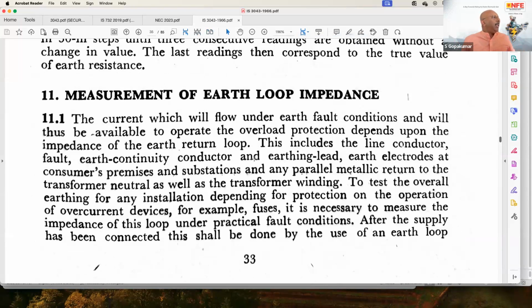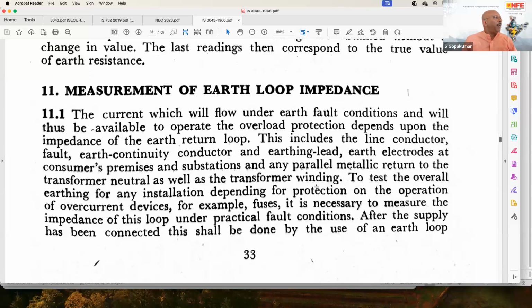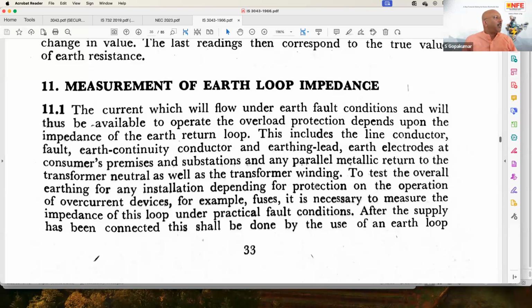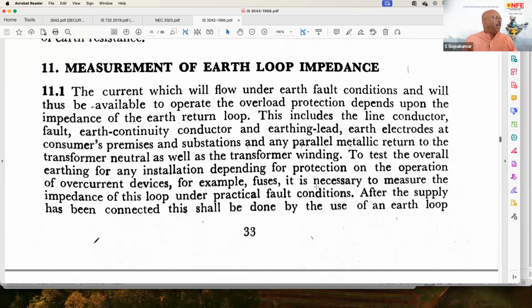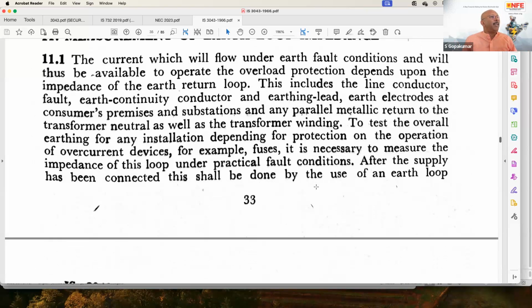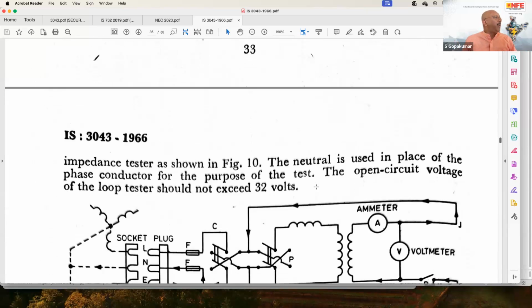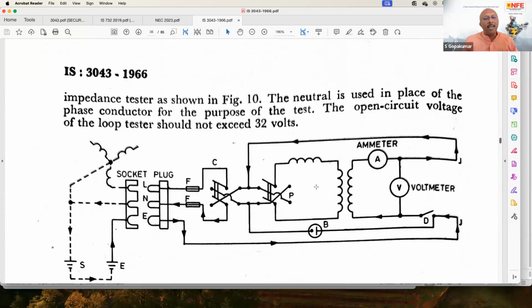So this includes the line conductor, the earth continuity conductor, and the earthing lead with the earth electrodes at the consumer premises and substation. So it is all the connections of this particular circuit. To test the overall earthing of any installation depending for protection on the operation of an overcurrent device, for example fuses, it is necessary to measure the impedance of this loop under practical fault condition. After the supply has been connected, this shall be done by the use of an earth loop impedance tester as shown in figure 10.